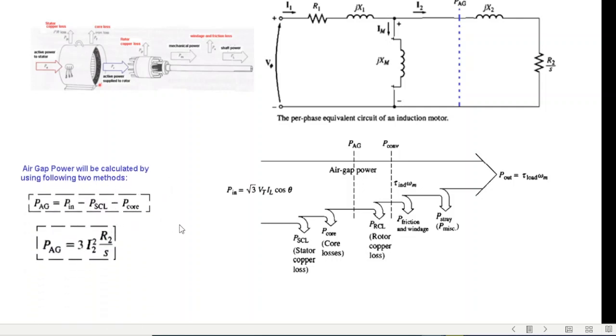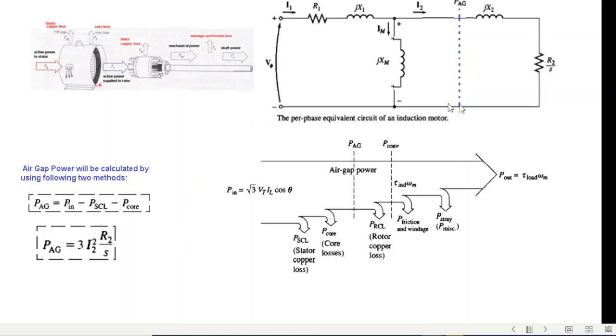Air gap power has two formulas. One is from the input side: input minus stator copper loss minus core loss gives the air gap power. The other way is to calculate from the output side: I2 squared multiplied by R2/s, where I2 is the rotor current. Since all powers are for the three-phase system and this is a per-phase diagram, we multiply by three. We'll be using both these formulas to calculate air gap power.